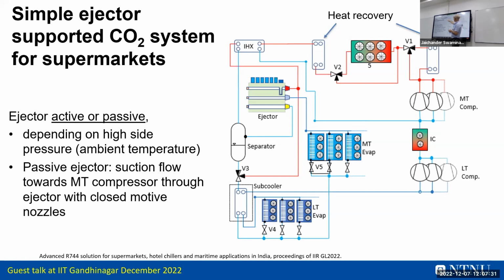When you have the cold temperature, you don't go to this expansion device, and so you go straight with the liquid to your evaporators, because they can deal with that. It's already liquid. And in the summer, the suction goes just through this device with maybe 0.2 bar pressure loss, but 0.2 bar is only 0.2 Kelvin in difference. So it's not the problem. That's the beauty. If you have a high pressure system, you can really deal with this and you don't lose much. So now some supermarkets will do this.